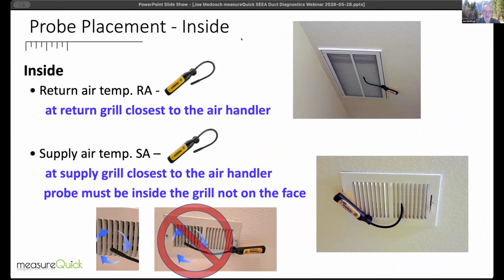So this is where duct leakage and a variety of other things get confirmed with the measurements that we have. We know your temperature and what your temperature split should be. If your ducts are in the attic and it's a hot day, we can give you an estimate that you probably have duct leakage because your temperature split's too high. You're bringing outside air into your ducts and your return's high, so we would give you that as a diagnostic. Our supply is actually in the register. We want really good temperatures from inside, not just what's on the face. So these are 2 of your indoor probes.